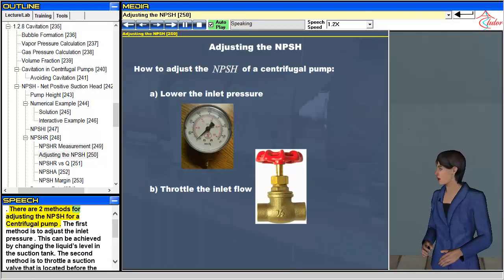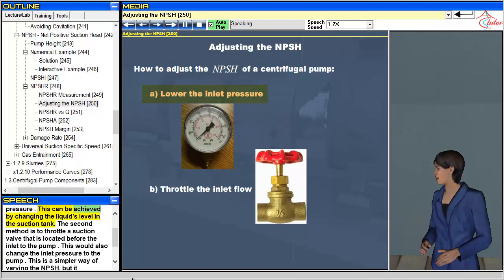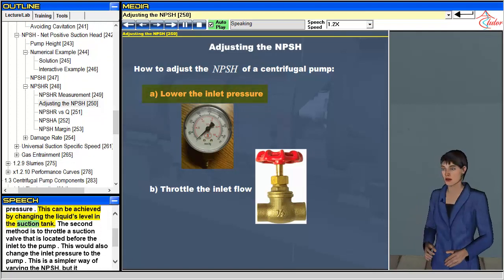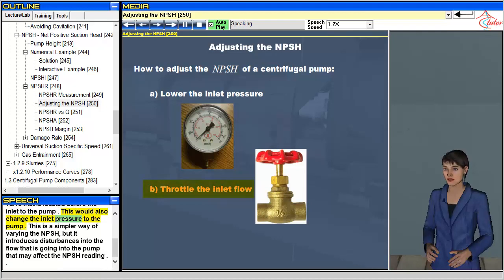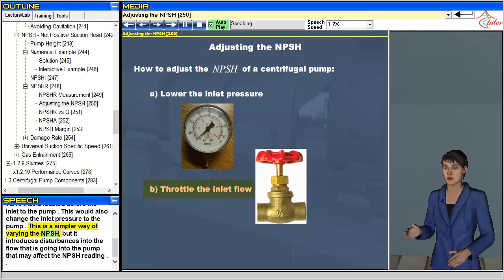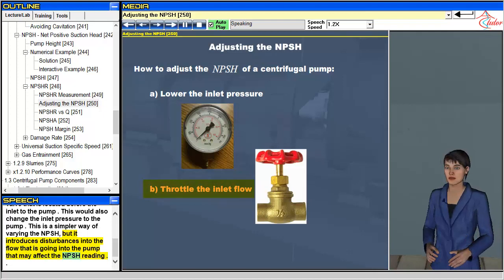There are two methods for adjusting the NPSH for a centrifugal pump. The first method is to adjust the inlet pressure by changing the liquid's level in the suction tank. The second method is to throttle a suction valve located before the inlet to the pump, which is a simpler way of varying the NPSH, but it introduces disturbances into the flow going into the pump that may affect the NPSH reading.